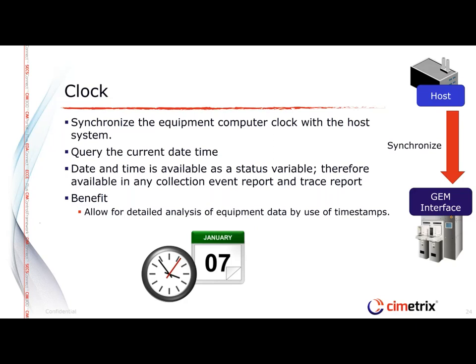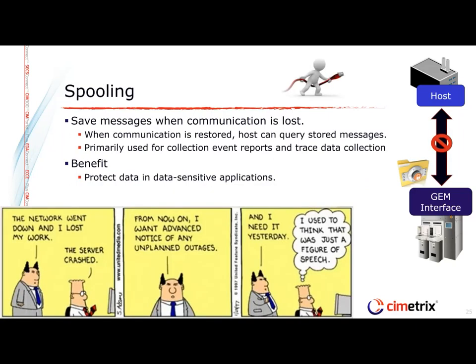There's also a clock feature in GEM for reporting the clock from the equipment. It allows the host system to synchronize the clock with the equipment, and by synchronizing clocks between the host and the equipment, data collection becomes significantly more useful because you can correlate data from one GEM interface to another. Without clock synchronization, you can't really correlate data from one piece of equipment to another or to other systems in the factory.